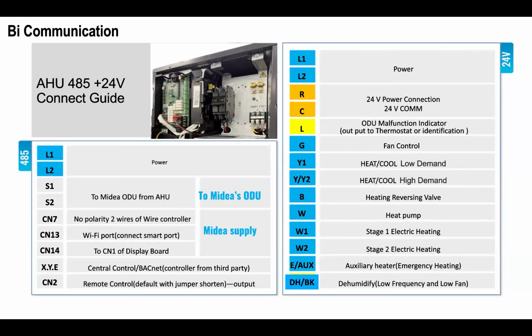CN14 is an interconnecting cable between the display and the main board. XYE is your central control or BACnet controller wiring. We don't personally offer a BACnet controller, but we have one that's made by Intesis for us, specifically for this machine. So it is available. CN2 is your remote control. That's your remote on/off for your front desk control.